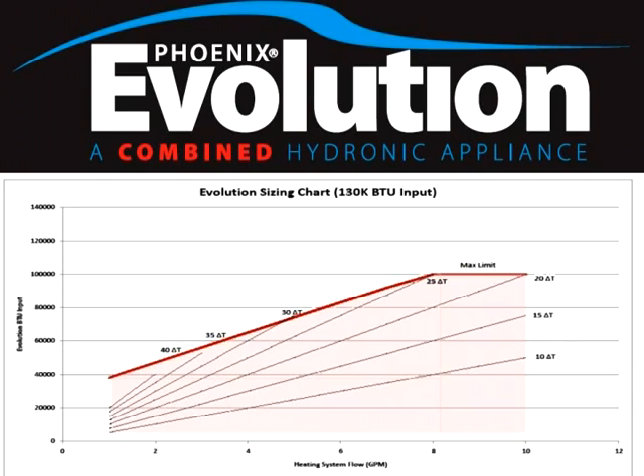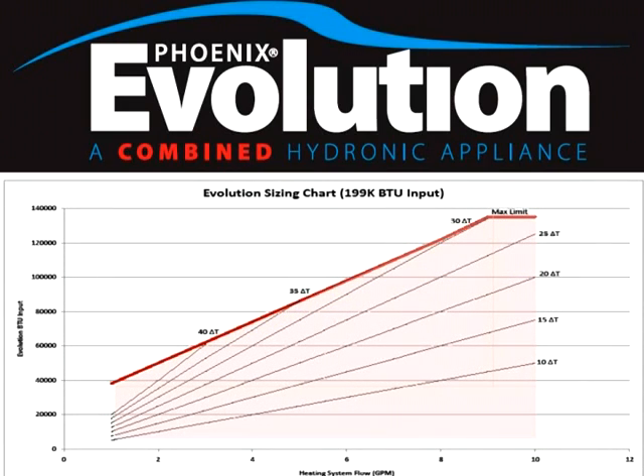In this case, we're looking at BTUs that can be extracted from this heat exchanger, and we're looking at the flow rate over on this side that would be going out to the system. And here are the various delta T's that can be operated at. So you can see that in a 130,000 BTU model of the Evolution, you can get about 100,000 BTUs at 20 degree delta T out of this unit. And correspondingly, on the 199,000 BTU unit, we can extract about 135,000 BTUs from the unit at a broad delta T, a 30 degree delta T, more like 120,000 in tighter delta T conditions, depending on what you've set up your system for, meaning going out to your heating system.